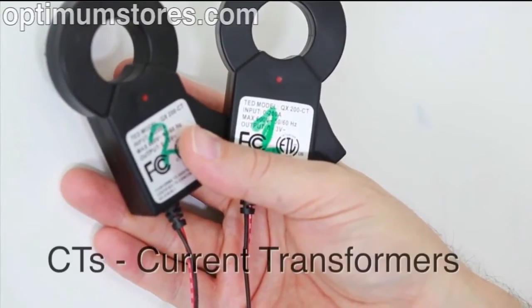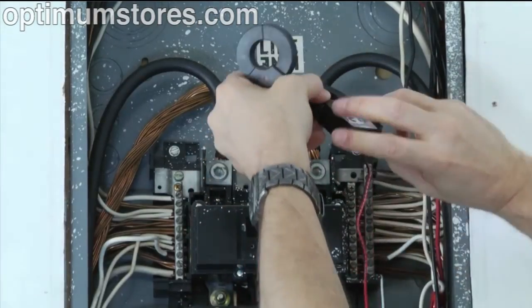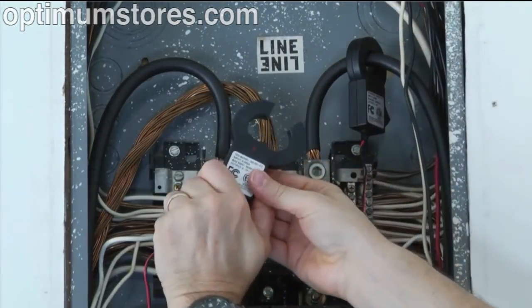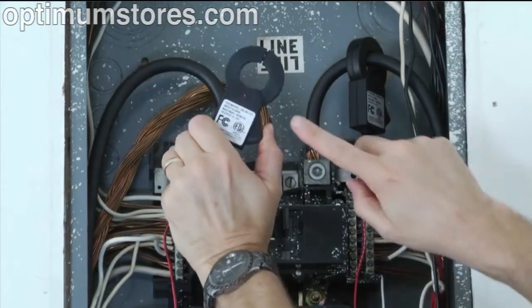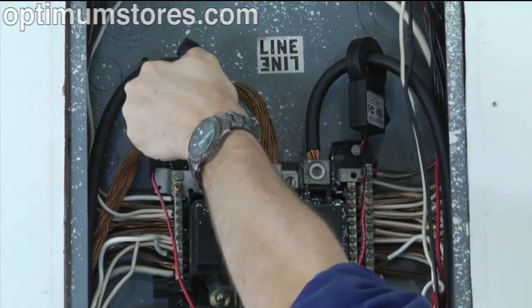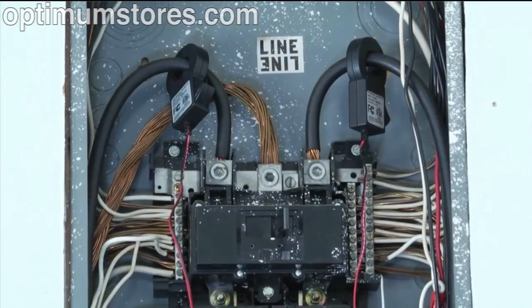Now that the MTU is installed, it is time to connect and install the current transformers. Install one CT over each incoming power line A and B by pressing on the handle to open the split core, then clipping it over the power line. The CTs must be installed with the red polarity dots facing toward the power source. If both CTs are not installed in this manner, the readings will be inaccurate.